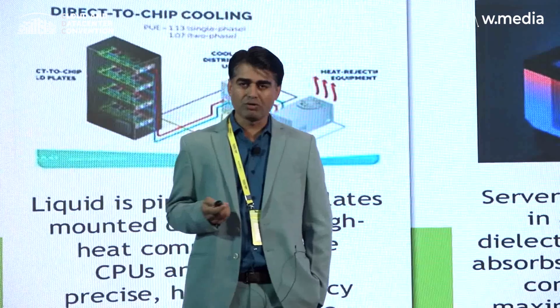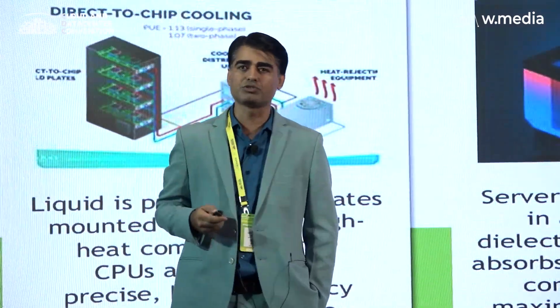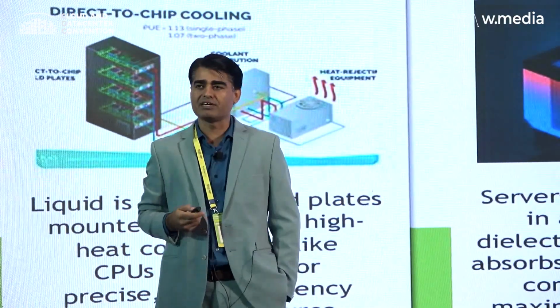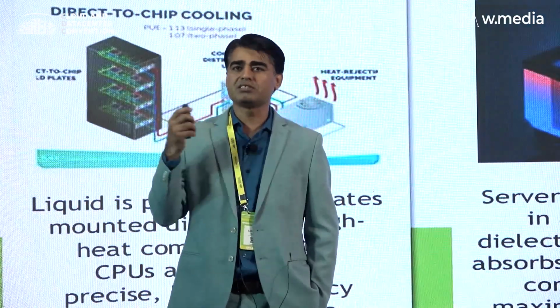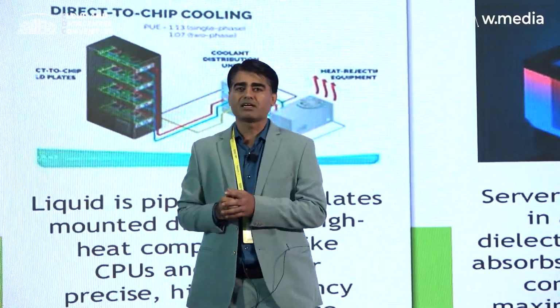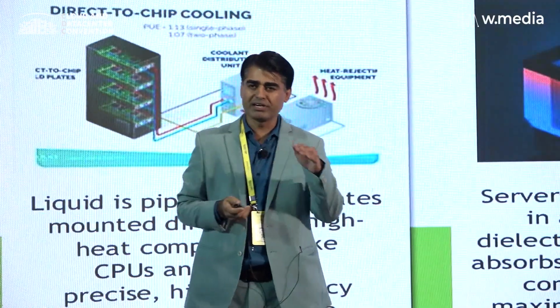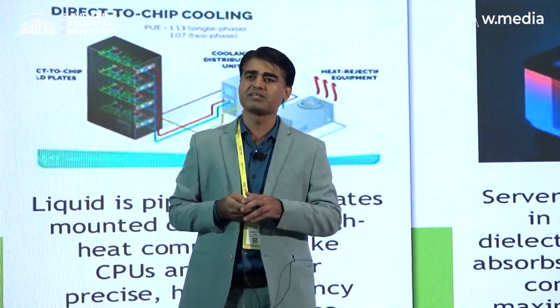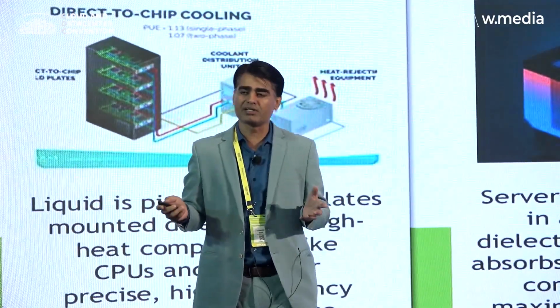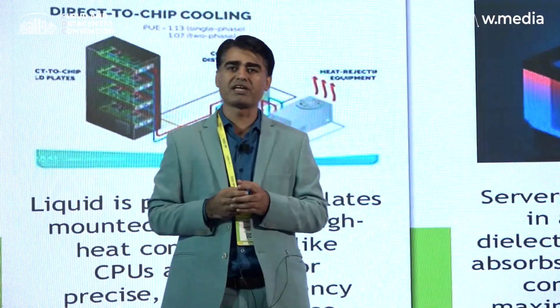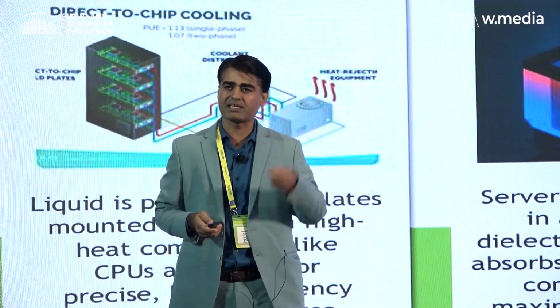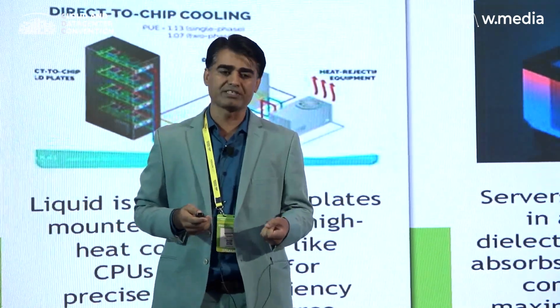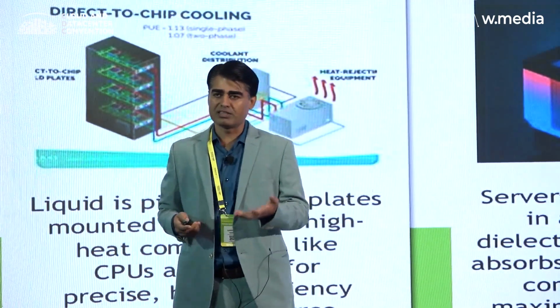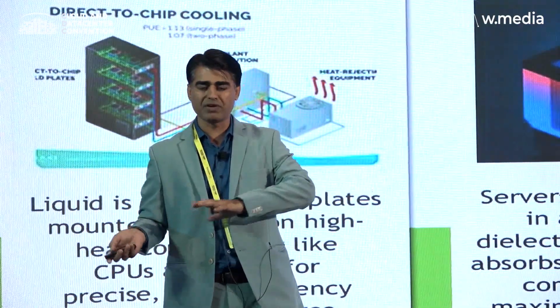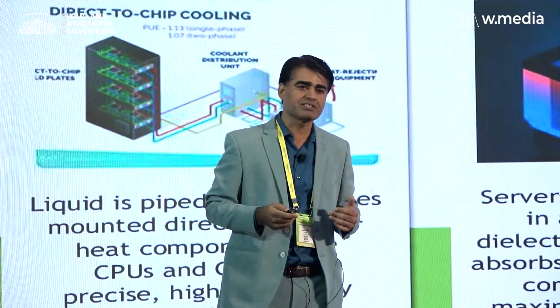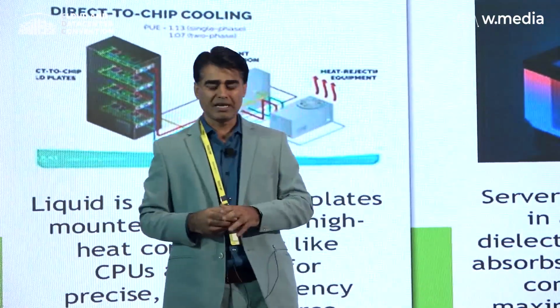So these technologies, liquid cooling, of course we've seen very good CDUs placed here in booths, or even right in front at some of the other stores. These CDUs and the entire secondary fluid network, coupled with cold plates mounted over the high heat generating components inside the server, form the basis of direct-to-chip liquid cooling. Secondly, there's immersion cooling, where we have immersion tanks, and all the server racks are placed inside, with the complete heat transfer taking shape within that immersion tank itself. That's immersion cooling, it could be single phase or multi-phase depending on how the heat transfer takes place and what fluid is used, and then heat exchangers.